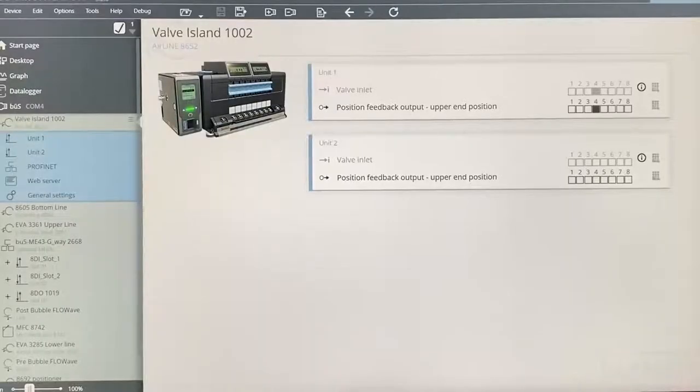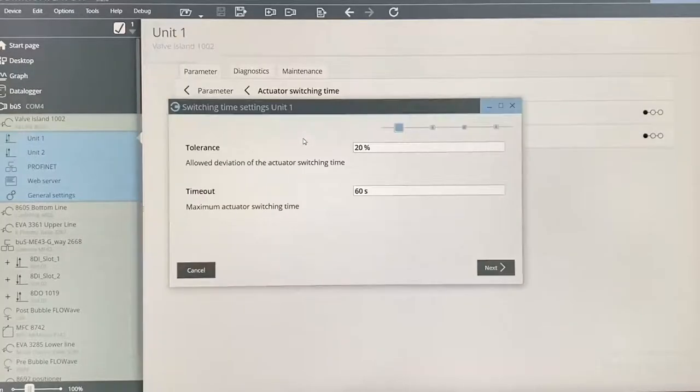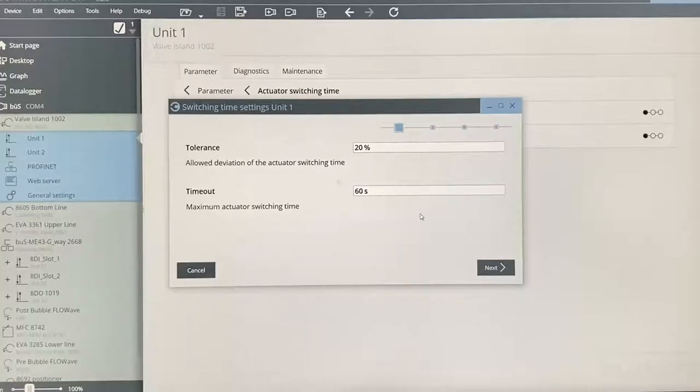You can check what result has been recorded, as well as adjusting any tolerances. To do that, go to settings and adjust the percentage tolerance value as necessary. If needed, adjust the timeout period. This is a value in which an error message will be generated should a feedback signal not be received in a normal time period. An example could be the complete failure of a pneumatic air supply, which would stop the valve from actuating and provide the feedback.